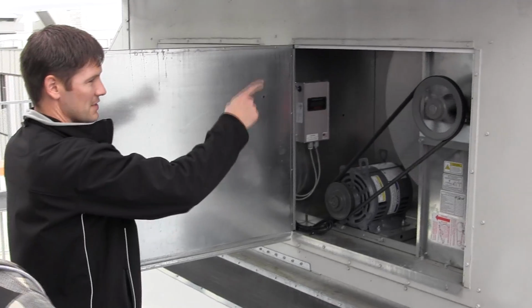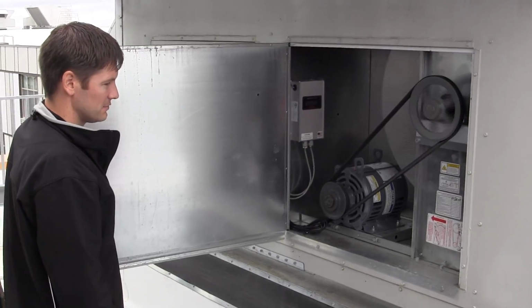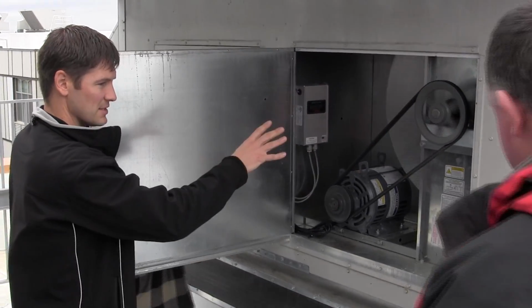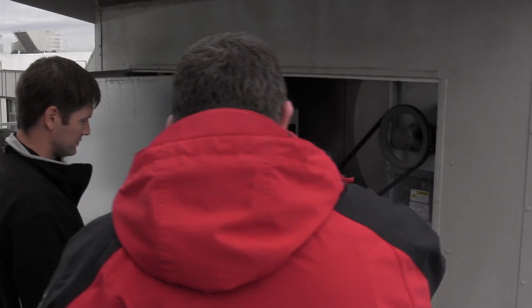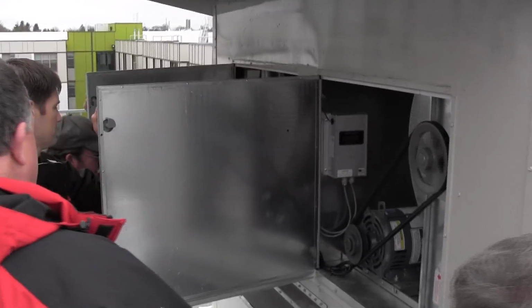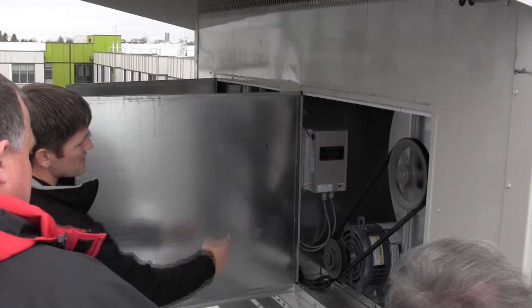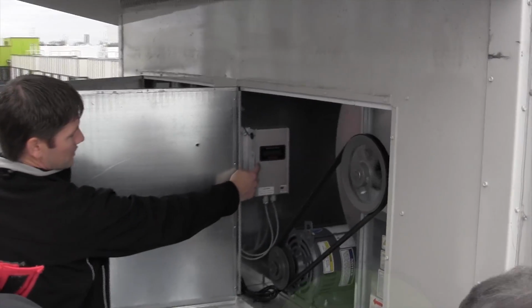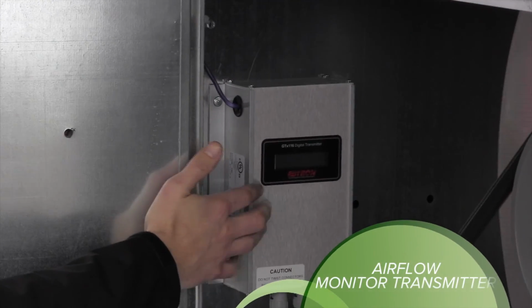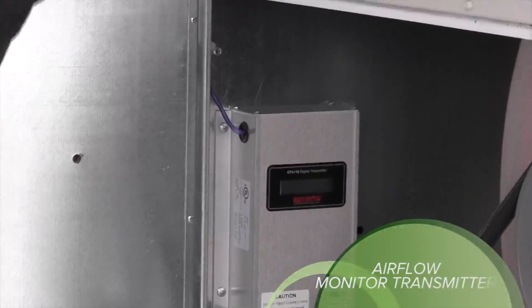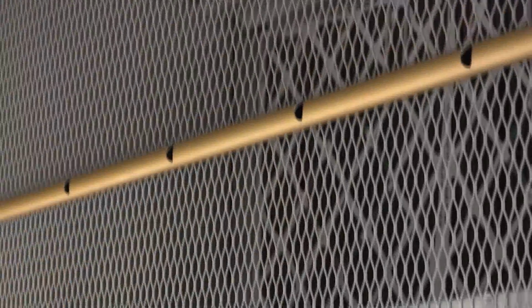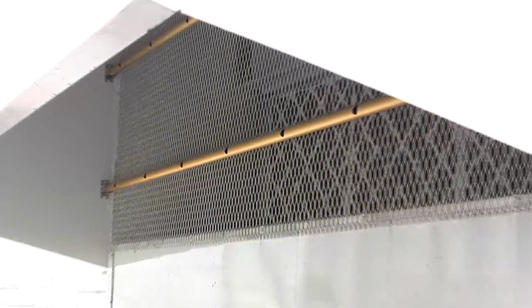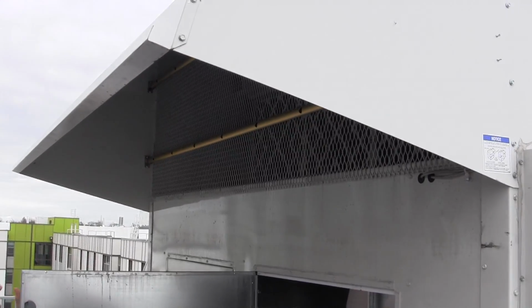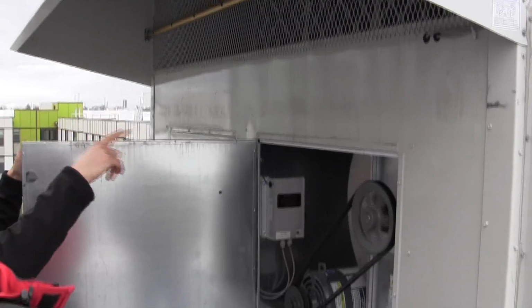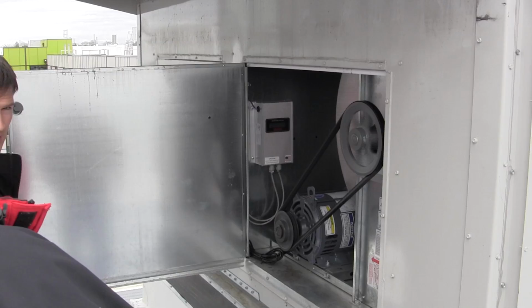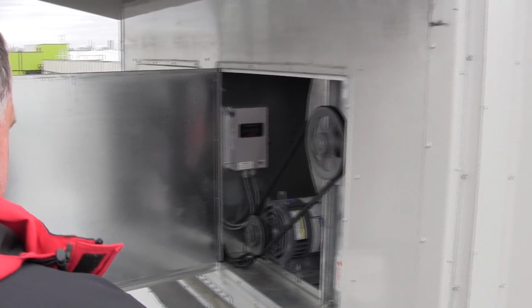Belt driven, but it is a plenum fan, backwards incline, pressurizes the cabinet, forces the air out. This is actually the airflow monitor transmitter. So it's reading the air that goes through each one of these holes, averages it, converts it to a feet per minute, and then the area of that opening is computed in here to give us a CFM, cubic feet per minute.